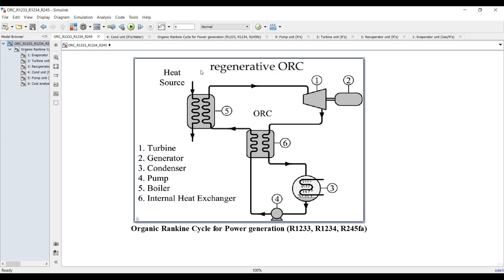You can attach the heat source to waste heat or process heat — it's up to your design. The input stream for the evaporator from the hot source is already known. I'm considering this as waste heat from any type of process. We have here an expander or turbine, a recuperator unit for regeneration, a condenser, and the stream from the condenser is pumped back through the recuperator to recover heat before going to the evaporator, in order to reduce the load on the heat source.